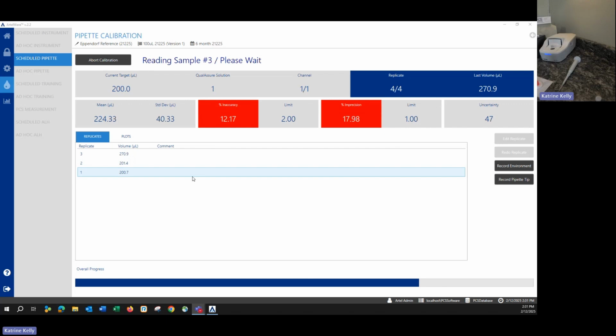So as soon as it took that reading, it recognized immediately that I'm over-delivering by quite a bit, and my indicators on the screen turn red. So visually, it lets you know right away that you've done something wrong. Now I'm going to go ahead and dispense my fourth and final data point. Pay attention to the right-hand side of the screen again for those two options that are still grayed out.